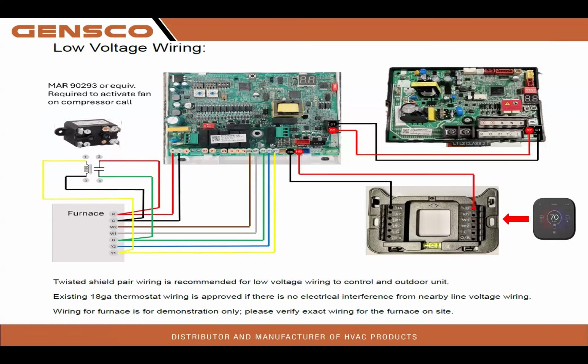Now, in the event that we are running dual fuel, notice we have added something to the scenario here. We have a MAR 90293 relay. So we have HAHB going to the mitigation control board. So we've got our HA and HB going to our mitigation control board. We've got our furnace and our 24-volt connections landed to the mitigation control board.